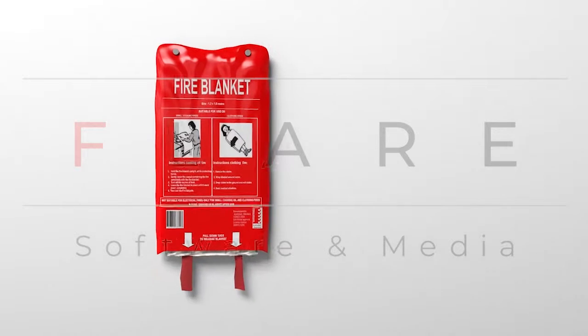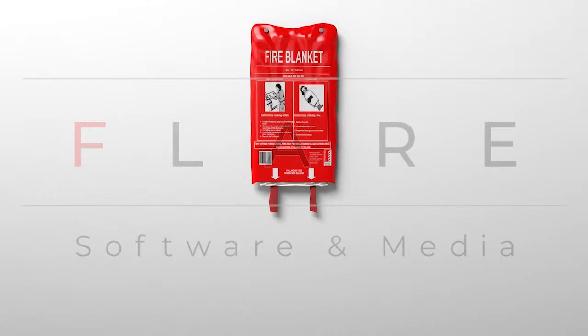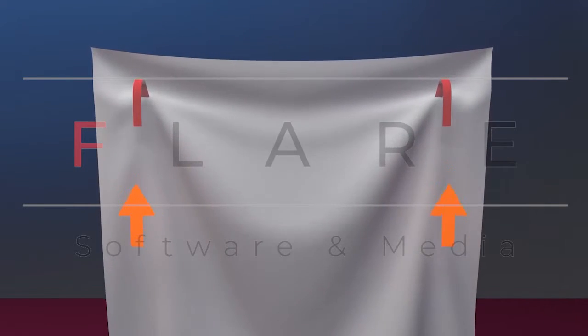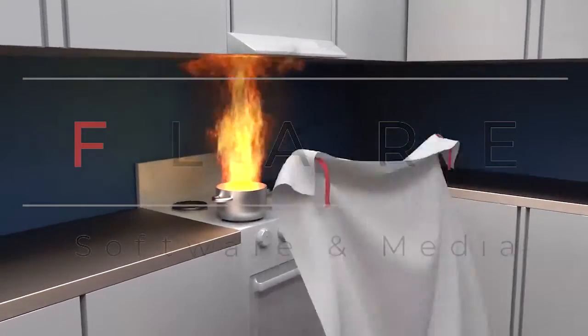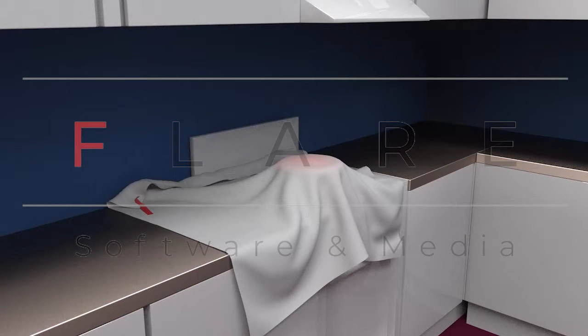A fire blanket cuts off a fire's supply of oxygen, smothering it either permanently or until more effective firefighting equipment can be employed. To use a fire blanket, pull down on the pull tabs. Unfold the blanket completely. Hold it in front of you to shield your body, hands, and face from the fire. Place the bottom edge of the blanket to the near side of the fire. Cover the burning material completely, ensuring there are no gaps for oxygen to reach the fire.